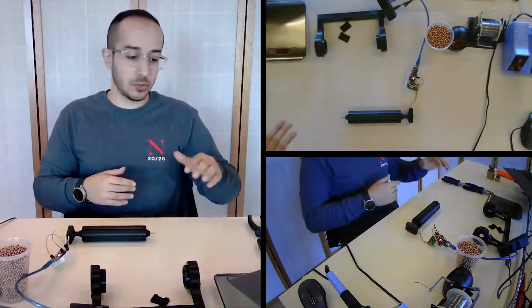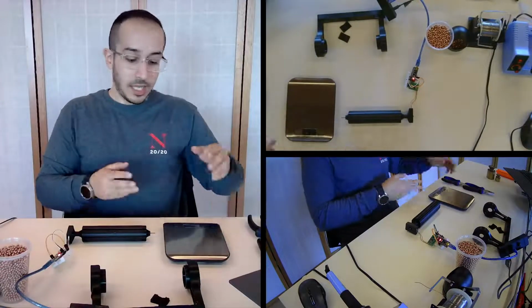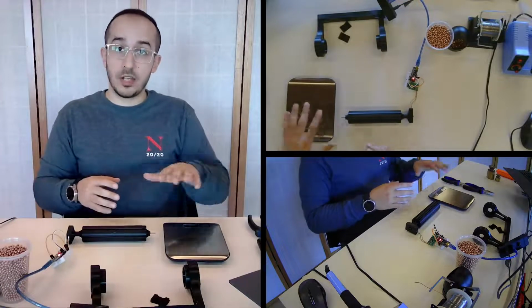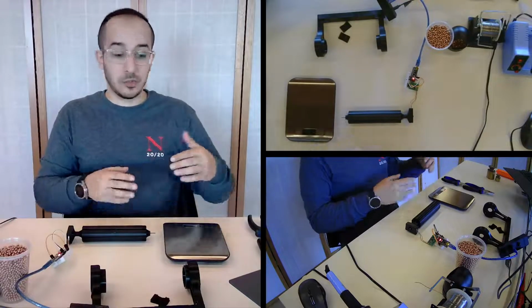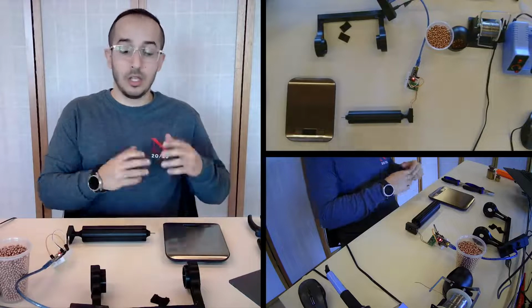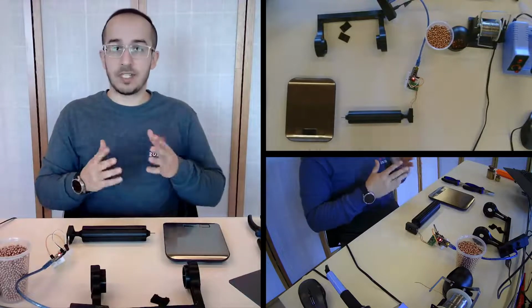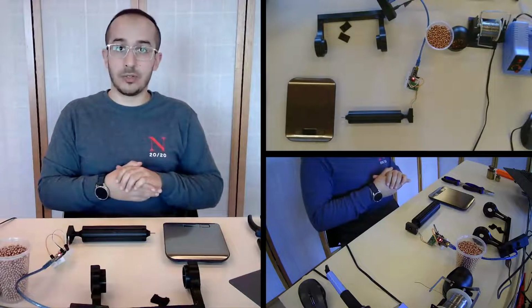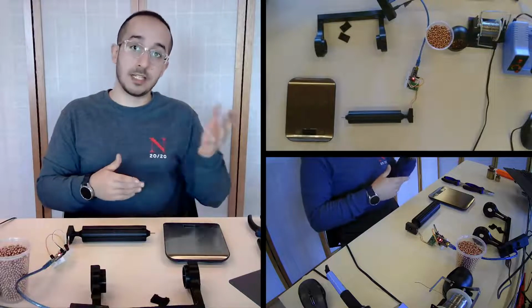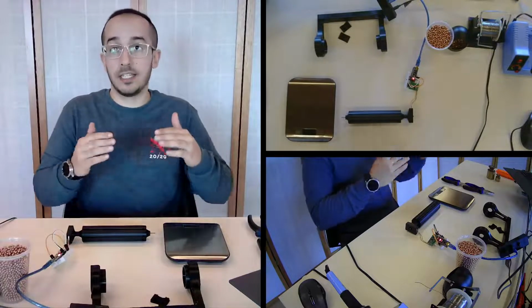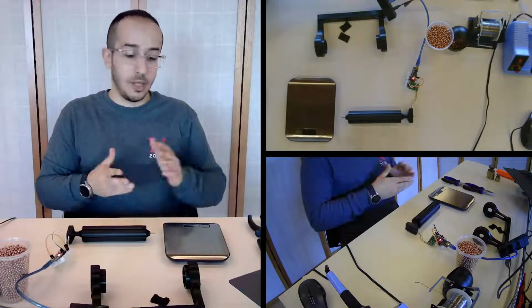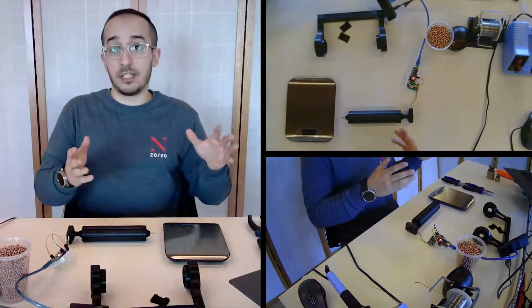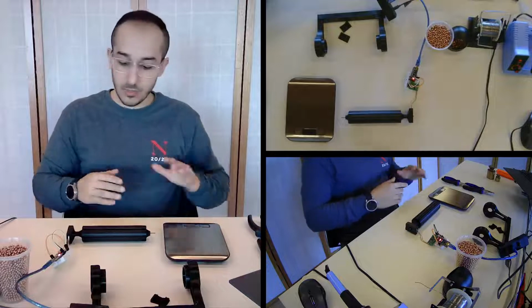For the calibration process, it is up to you what method you want to use and depending on what devices and tools you have access to. Perhaps the simplest one is to use a standard kitchen scale. And we will apply load to the device on the scale and compare the sensor output to the reading of the scale. Of course, you can use more sophisticated methods. For example, in our work, we used an Instron machine, which has high accuracy and high fidelity in applying different levels of loads. But this method could also work depending on the level of accuracy you want from the device.